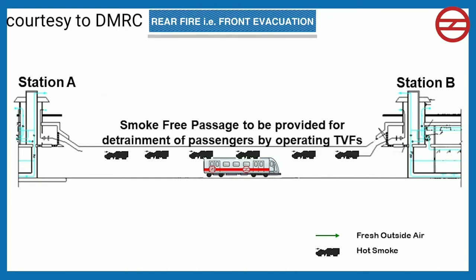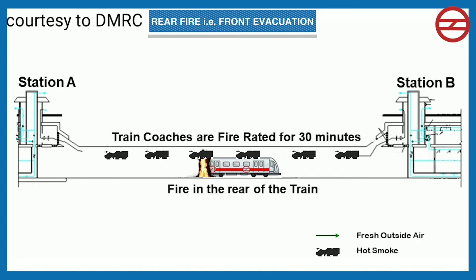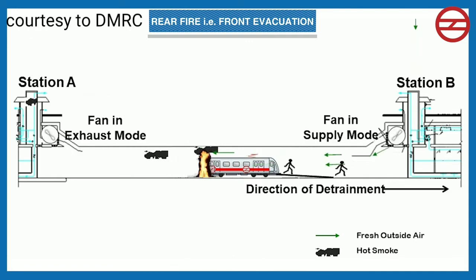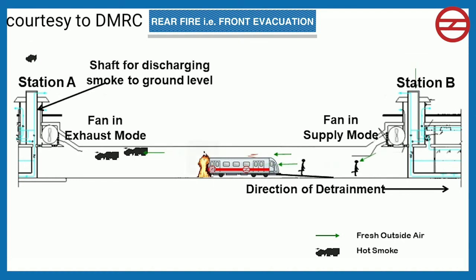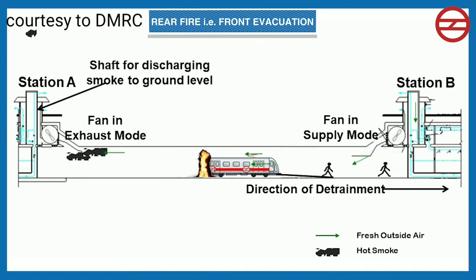Let's first see the case of rear fire, that is, front evacuation. In case of fire in the rear of a train, operator will plan for detrainment of passengers from front of the train. In this case, the TVF of next station will run in supply mode and TVF of rear station will run in extract mode. This will cause the smoke to move towards the rear station and passengers will be able to evacuate to the next station in a smoke-free environment. Tunnel ventilation system also consists of a shaft going up to the ground level. The smoke going to rear station will be discharged to the atmosphere through this shaft.